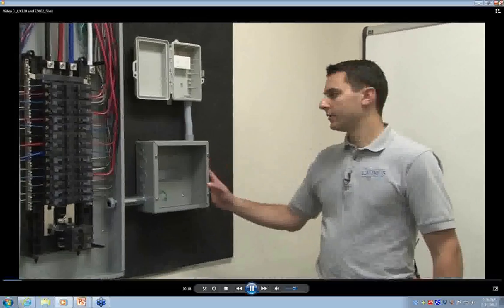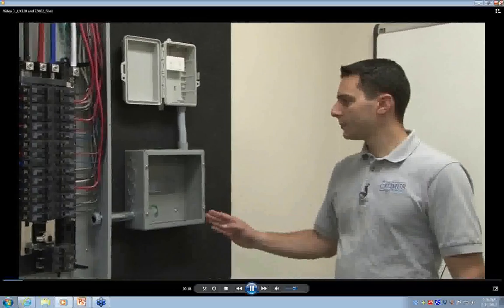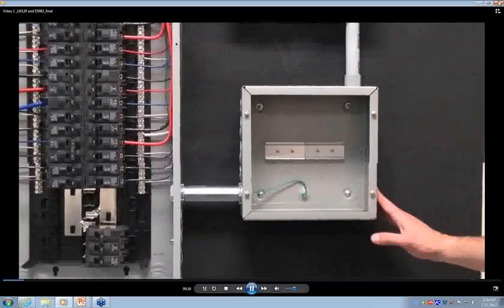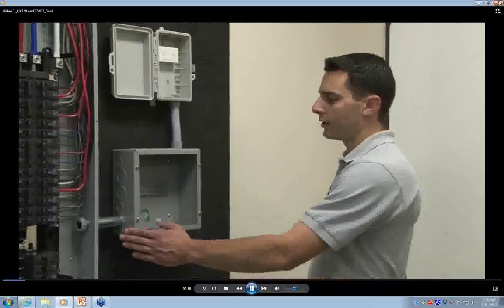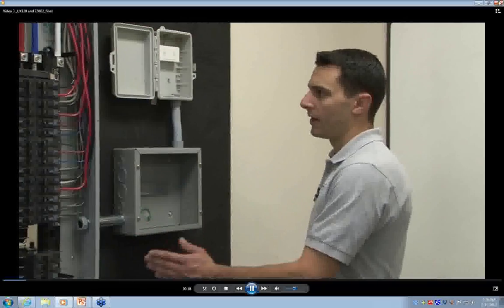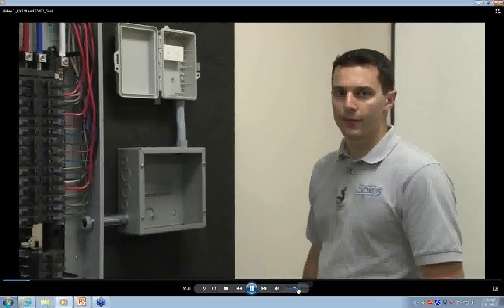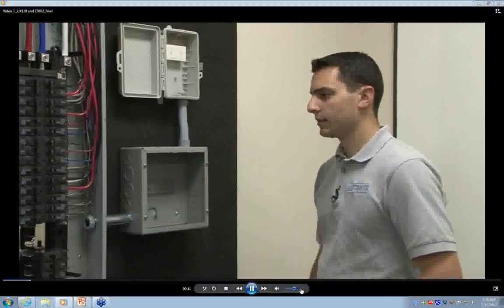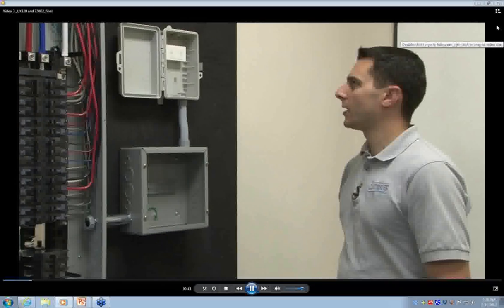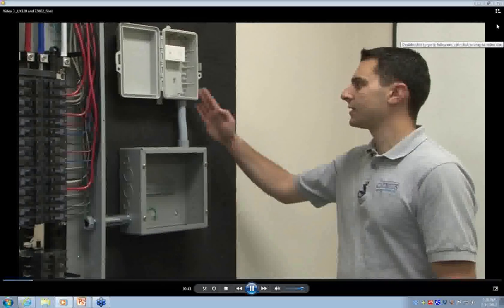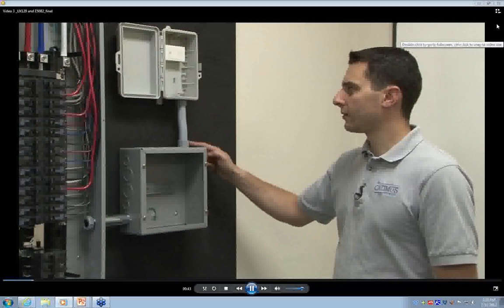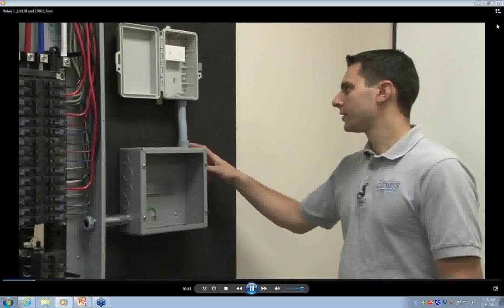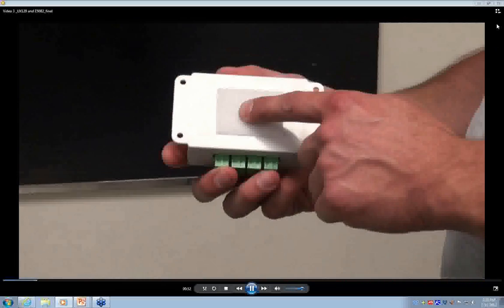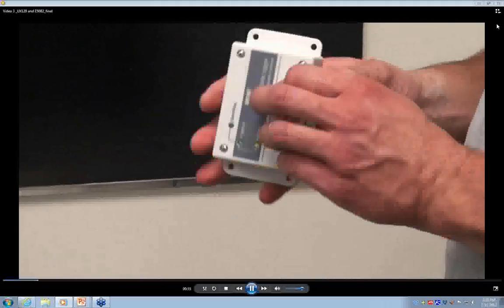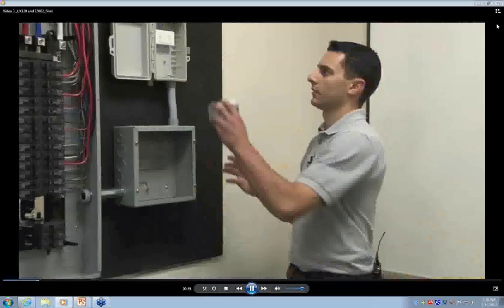For the E50B2, we'll install a standard 10-inch by 10-inch by 4-inch metal enclosure. We'll run a 1-inch conduit between the enclosure and the panel board for our 5 voltage leads and 6 CT conductors. For our UX120, we'll install a plastic enclosure with a plastic 3/4-inch conduit for our 6 communication conductors. For this installation, we'll use the Velcro mounting method in order to have ample space for our data connection.